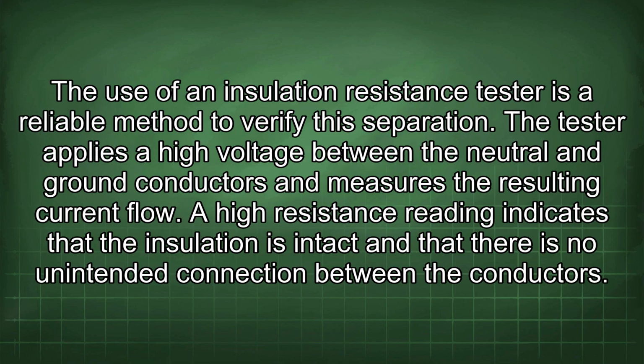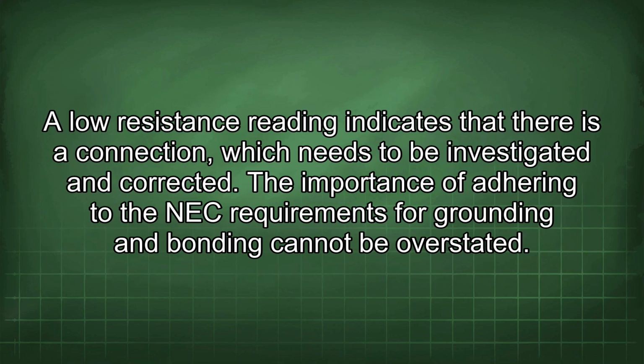The use of an insulation resistance tester is a reliable method to verify this separation. The tester applies a high voltage between the neutral and ground conductors and measures the resulting current flow. A high resistance reading indicates that the insulation is intact and that there is no unintended connection between the conductors. A low resistance reading indicates that there is a connection, which needs to be investigated and corrected.